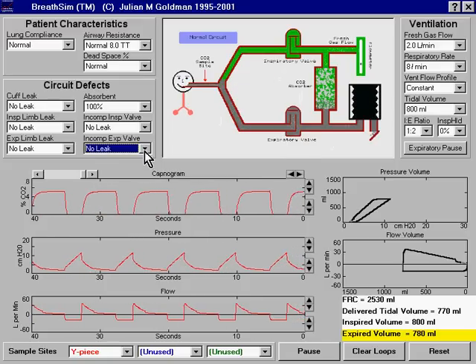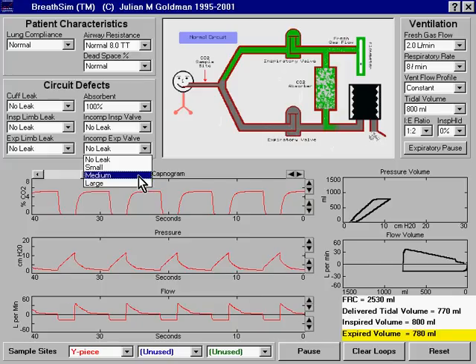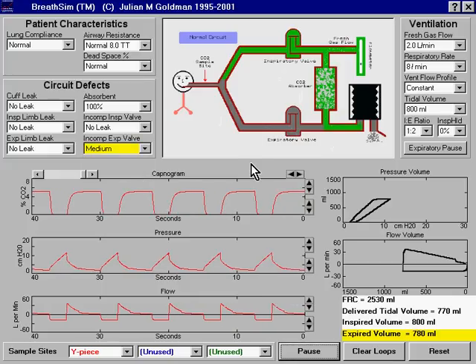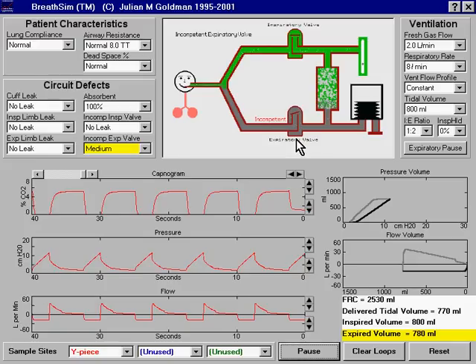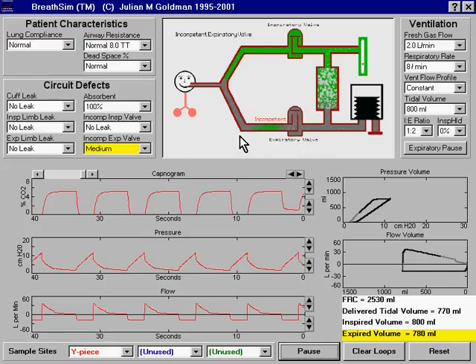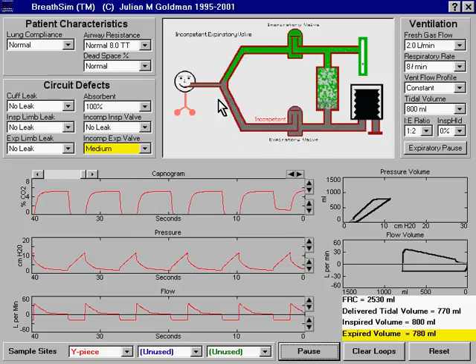So when the expiratory valve is incompetent, previously exhaled gas that fills the ventilator bellows is now able to be pushed backward down the expiratory limb and be rebreathed at the Y piece.